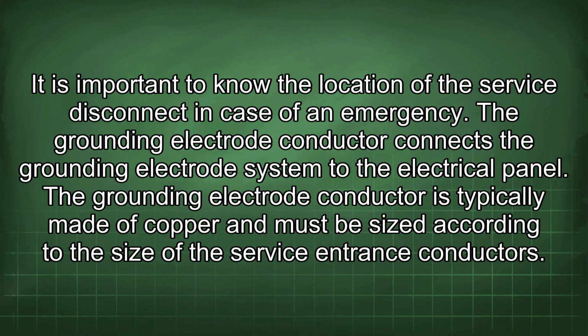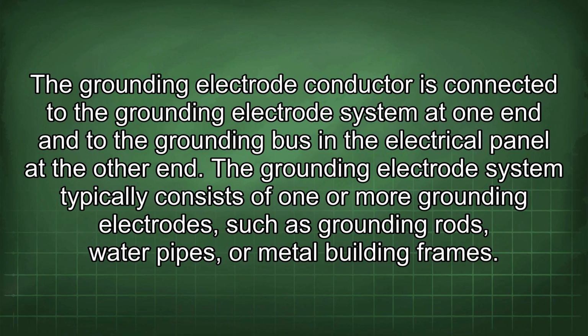The grounding electrode conductor connects the grounding electrode system to the electrical panel. The grounding electrode conductor is typically made of copper and must be sized according to the size of the service entrance conductors. The grounding electrode conductor is connected to the grounding electrode system at one end and to the grounding bus in the electrical panel at the other end.